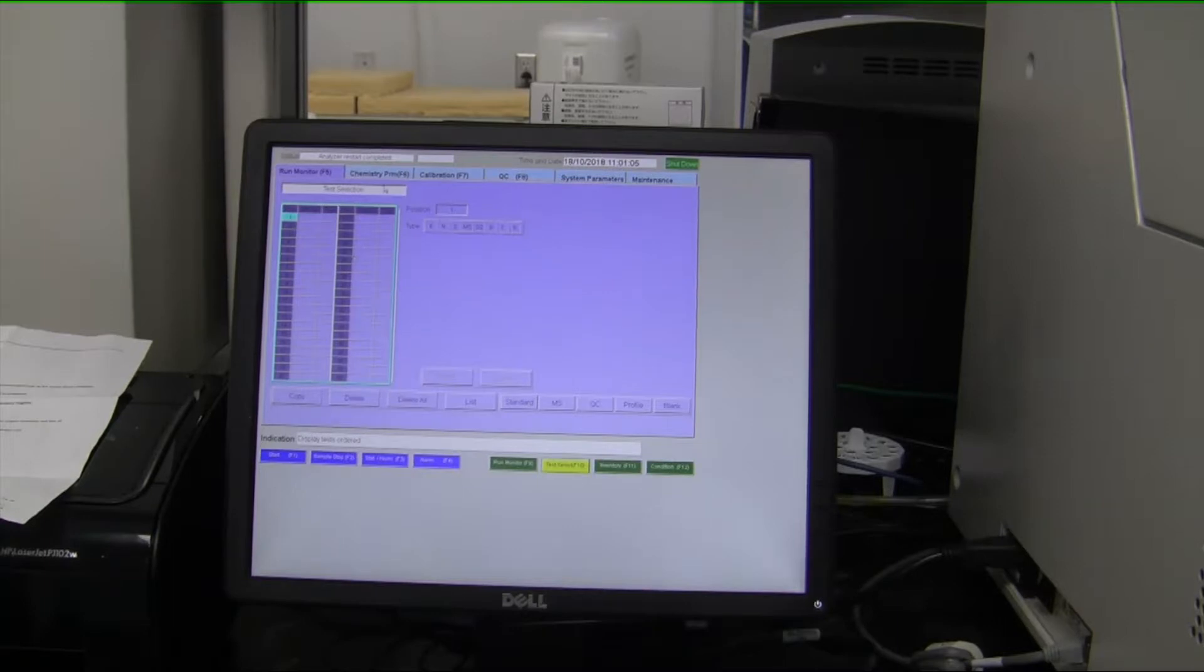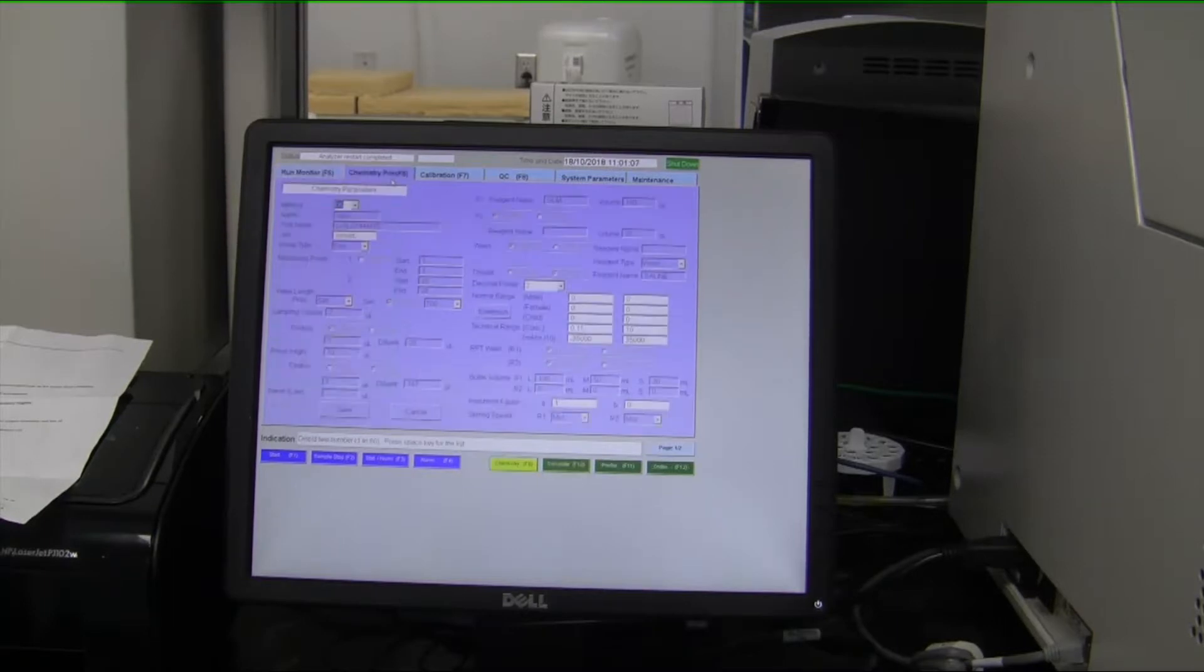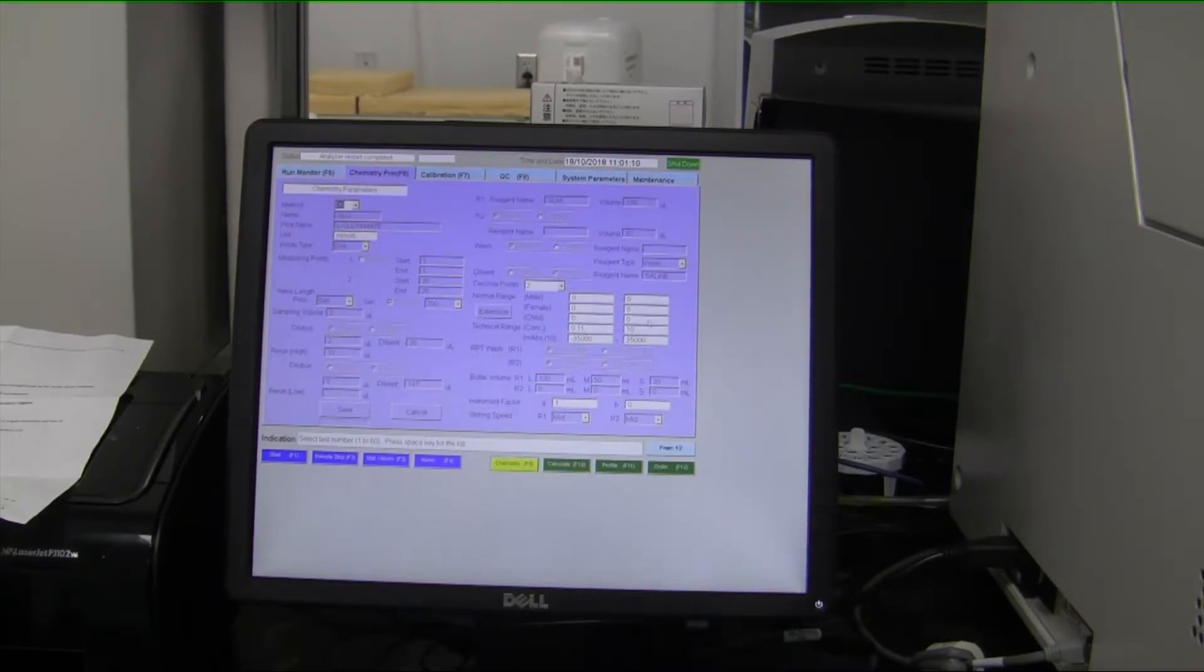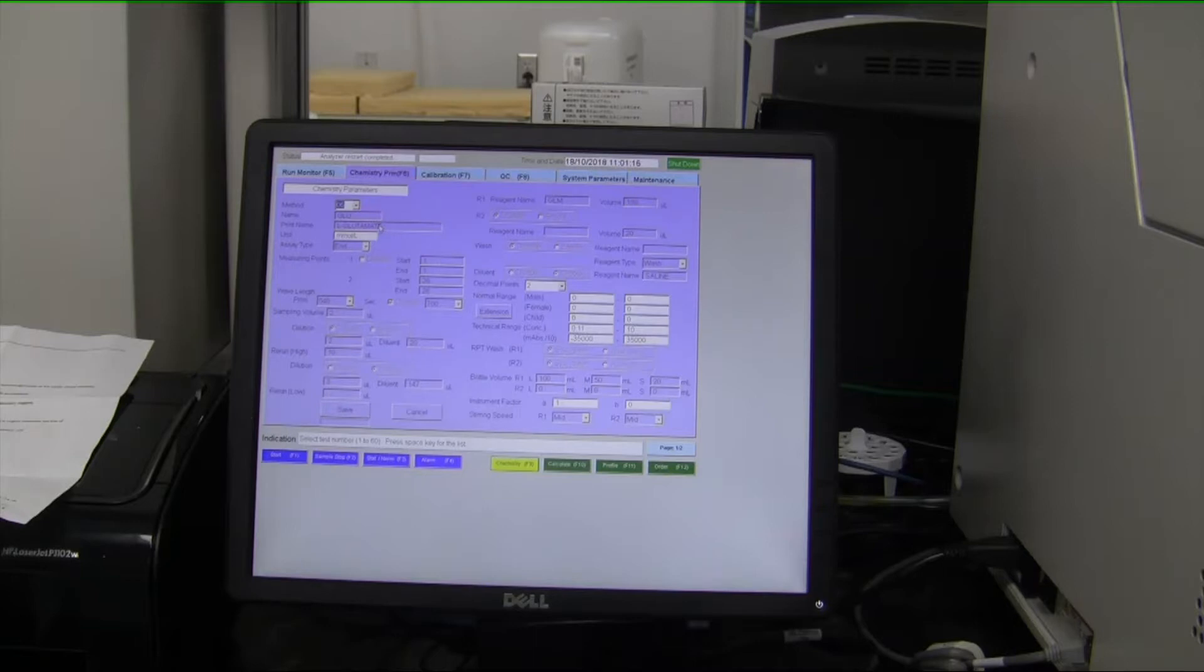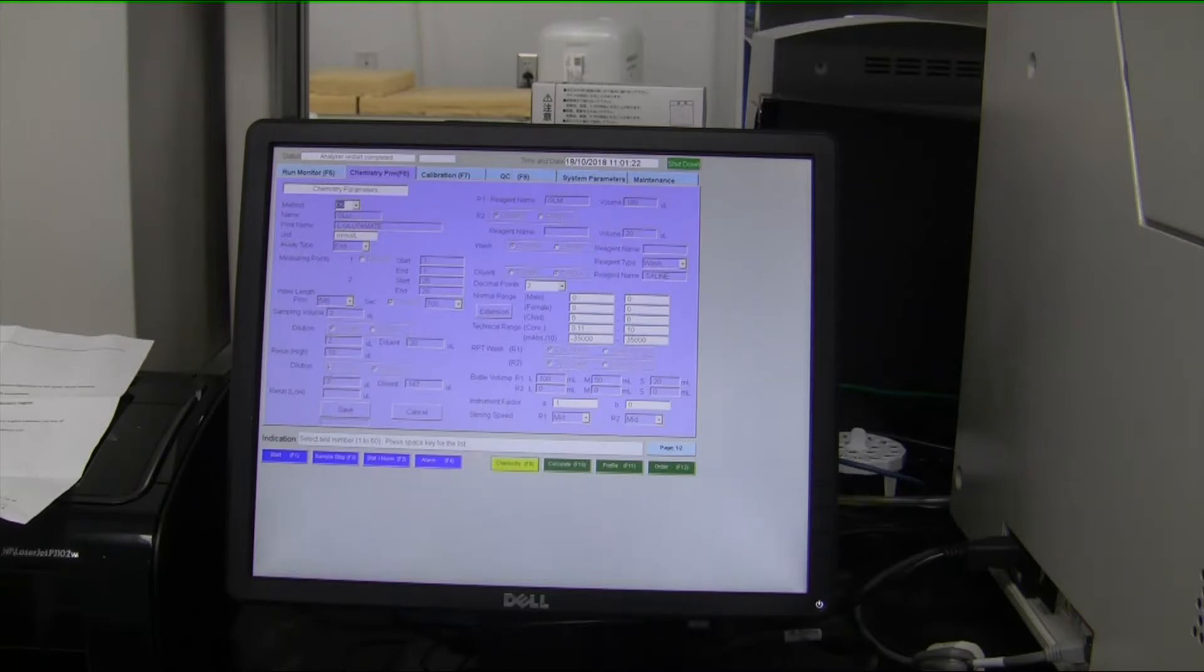If you wanted more advanced information about what the machine is doing in the background, chemistry parameters will tell you all about each specific metabolite, what its measurement units are, how much sample, and how much reagent is being put into the cuvette, and what specific optical frequency at which the measurement is being done. These things are all being done in the background of the instrument.